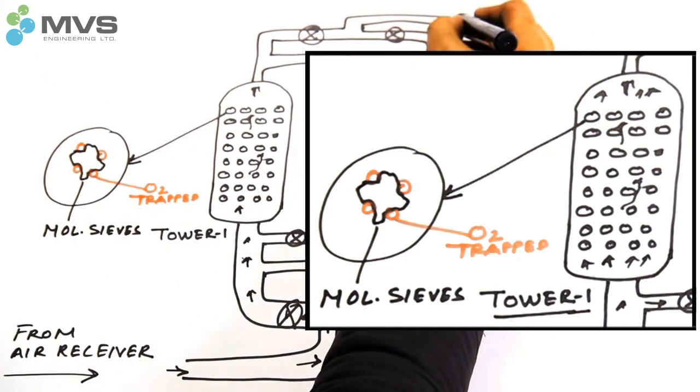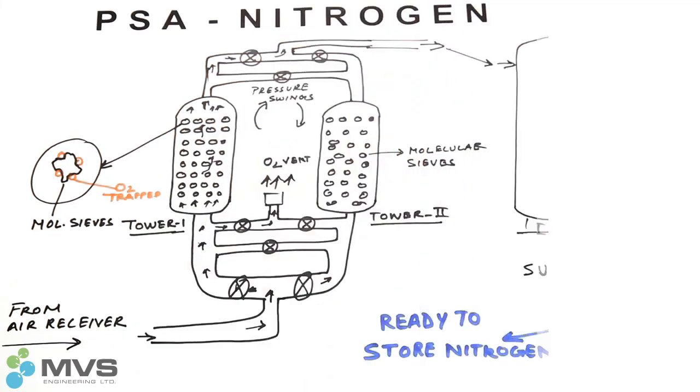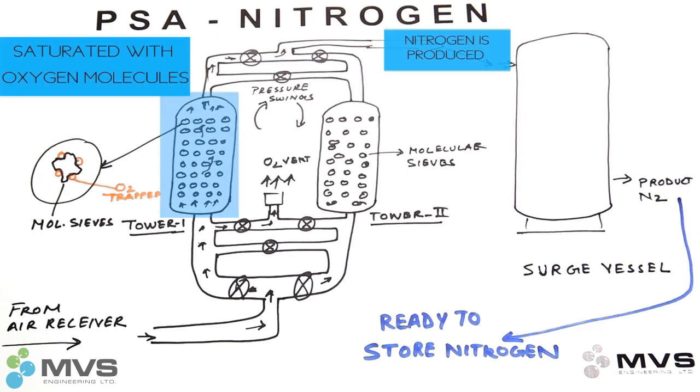The nitrogen molecule being bigger is unable to be trapped and hence gets delivered as a product nitrogen gas from this tower. The nitrogen production continues till tower 1 gets saturated with oxygen molecules.